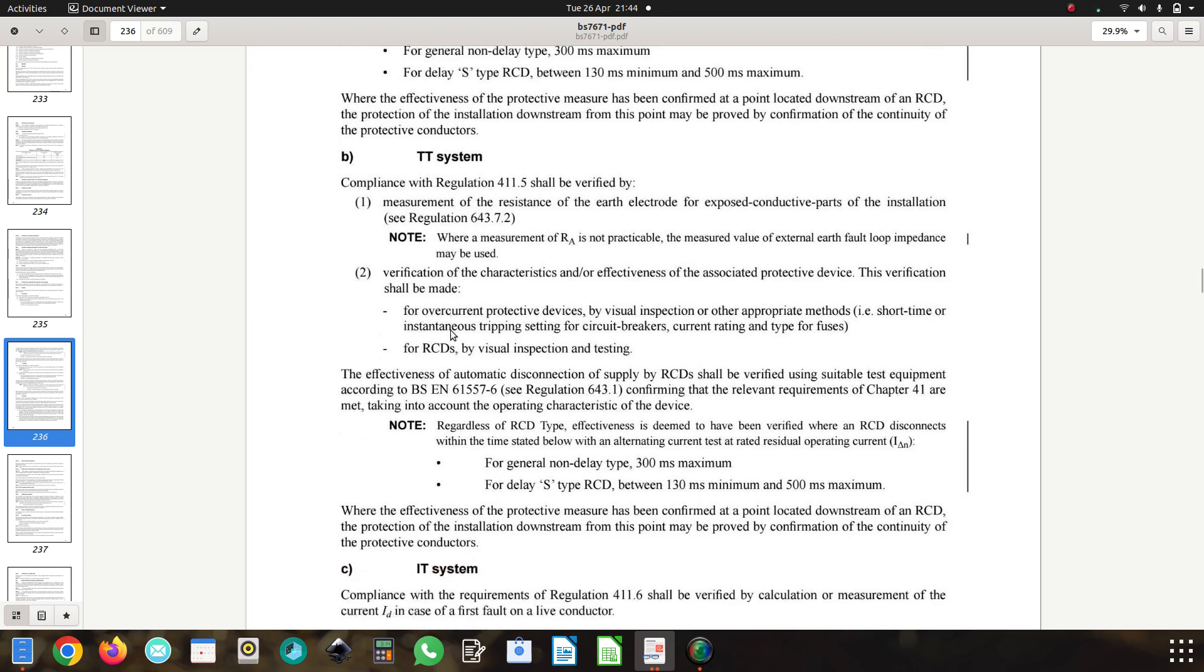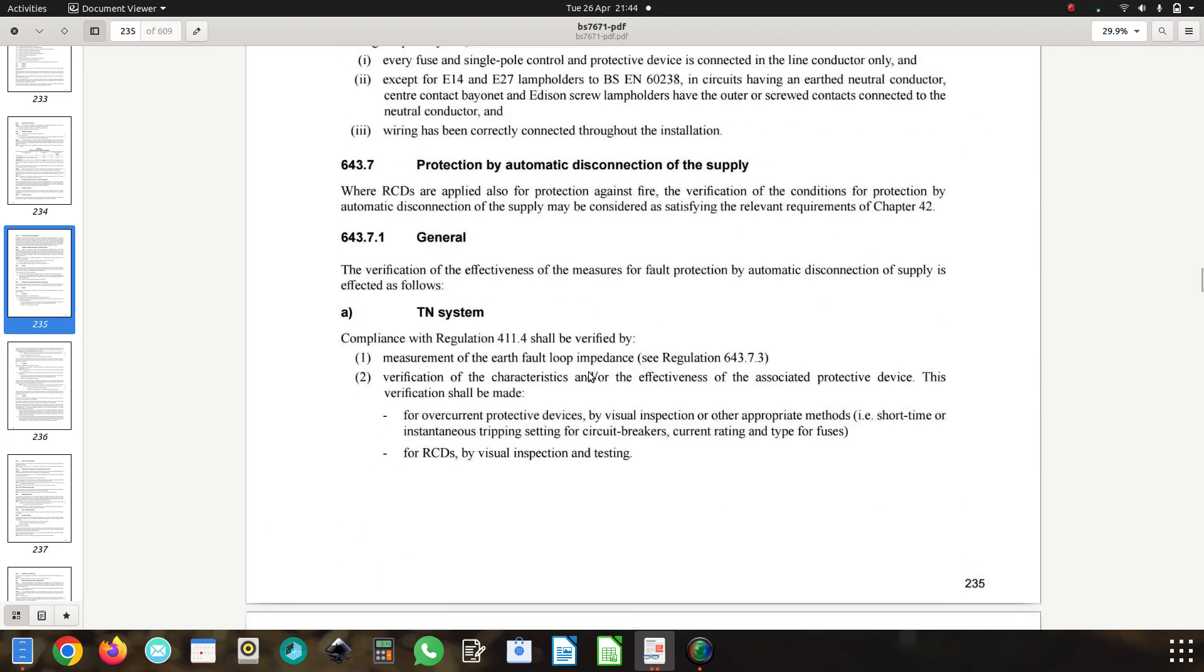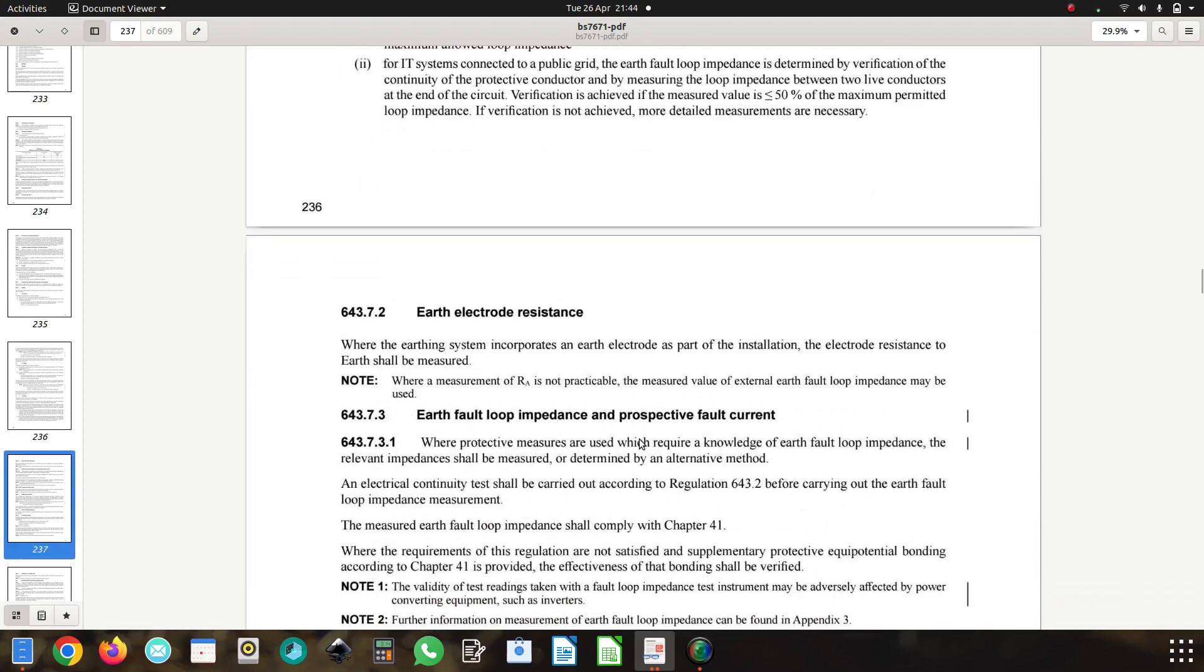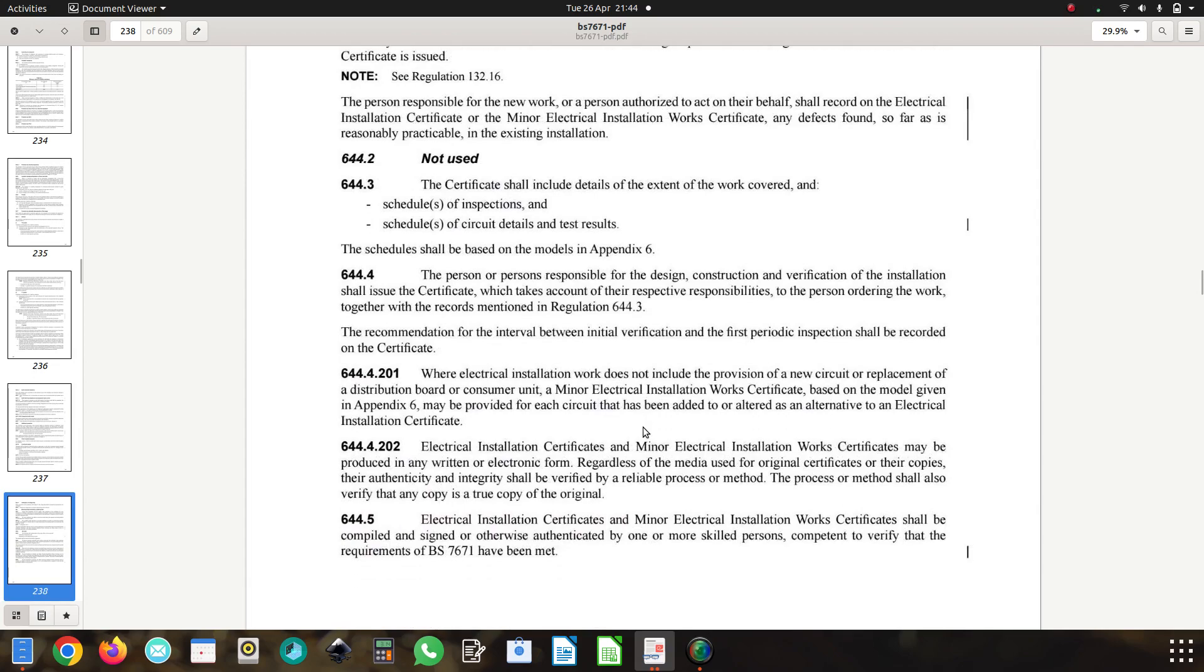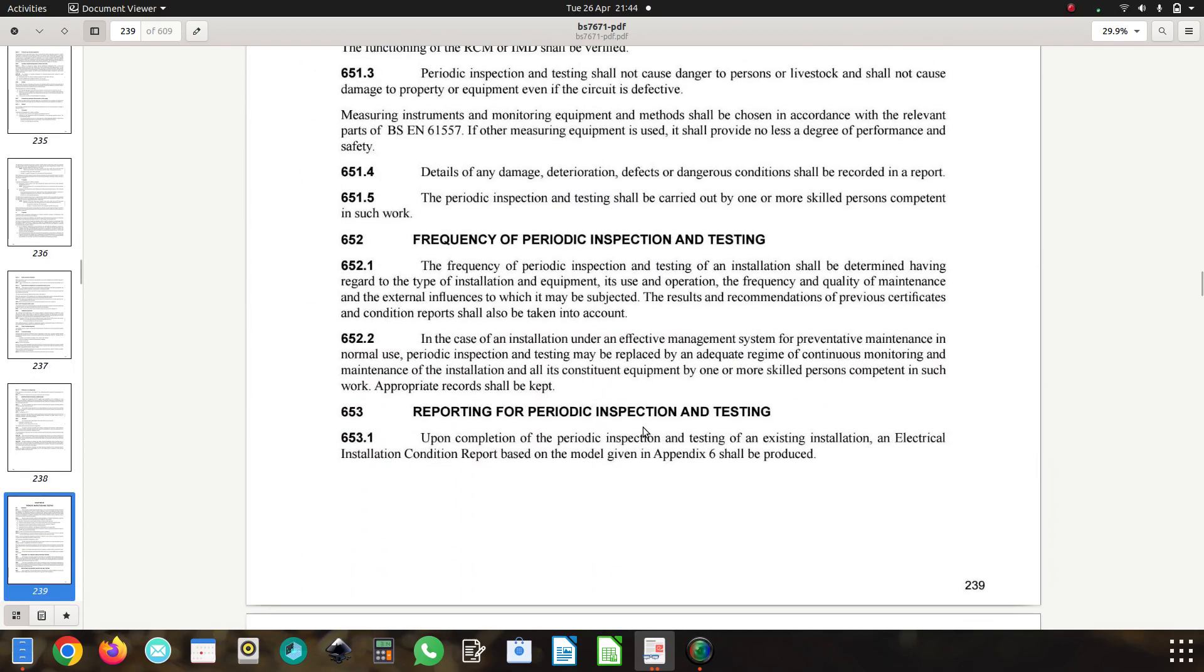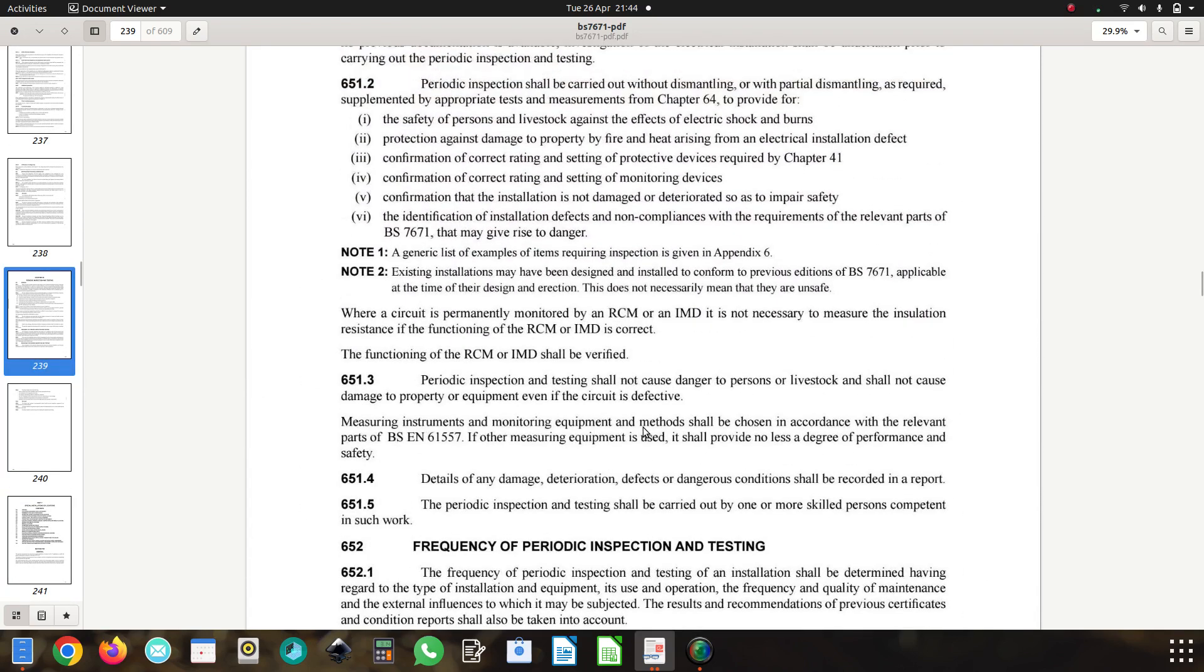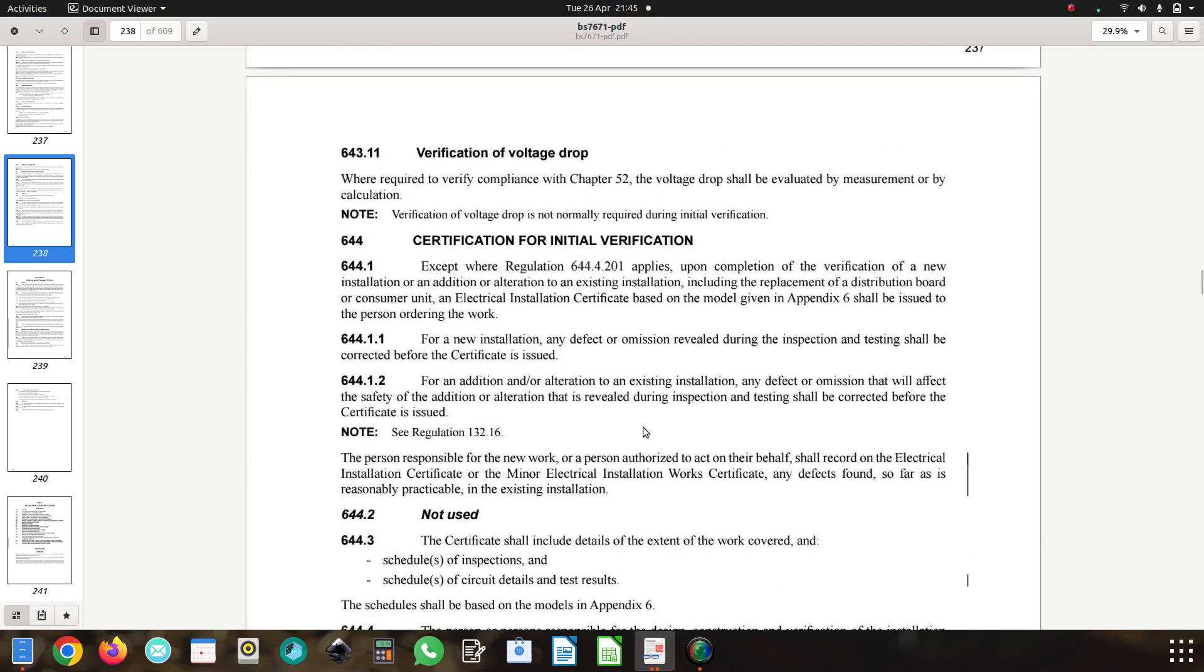So interested to know your thoughts guys on it. I think that should be 200 and leave the TN systems at 300. This is initial verification, and it's replicated in periodic inspection, requiring a figure of 300 milliseconds. It perhaps just needs to be reworded.